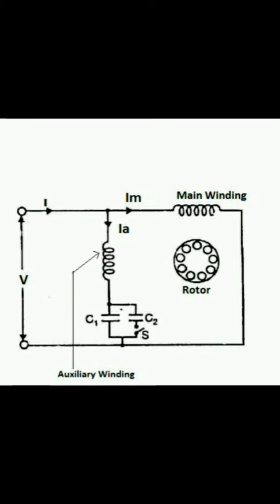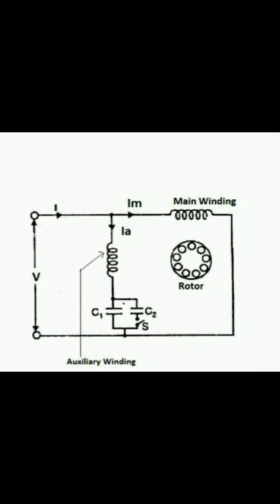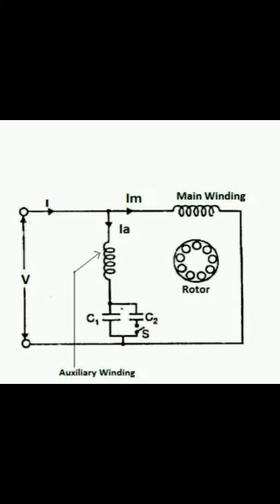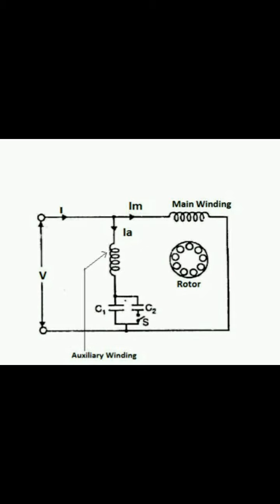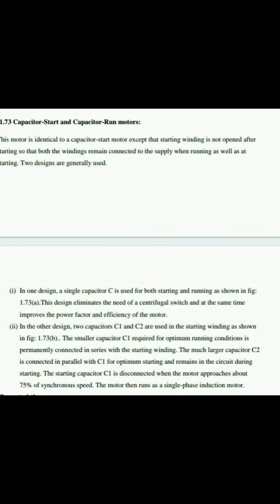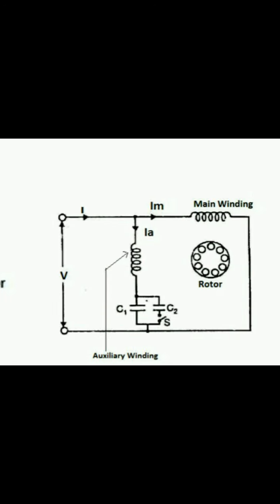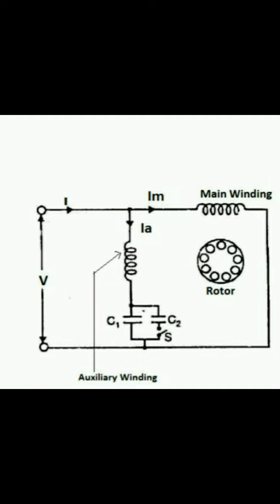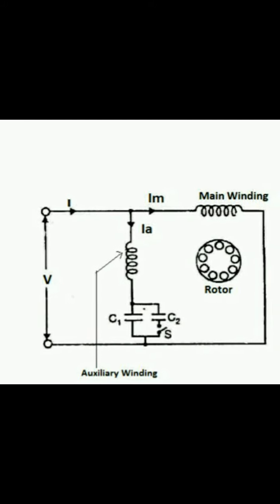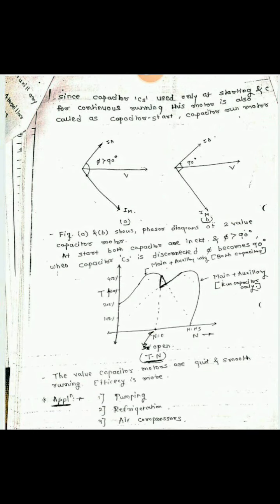C2 remains in the circuit during starting. The starting capacitor C2 is disconnected when the motor approaches about 75% of synchronous speed, and the motor then runs as a single-phase induction motor. As shown in the figure, S is a centrifugal switch. Capacitor C1 is available during both starting and running conditions, which is why this motor is called the capacitor start and capacitor run motor.